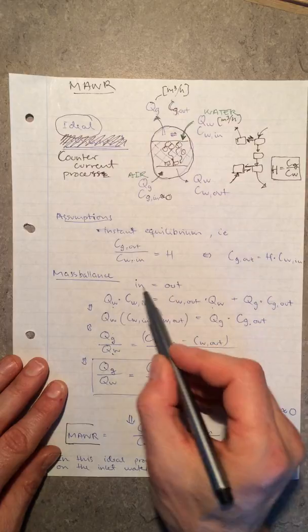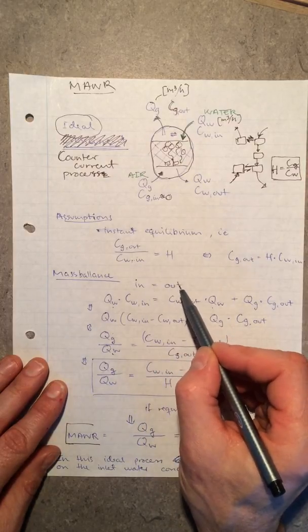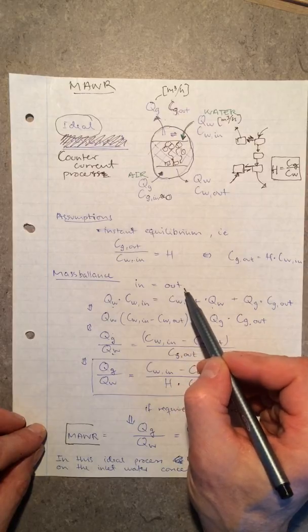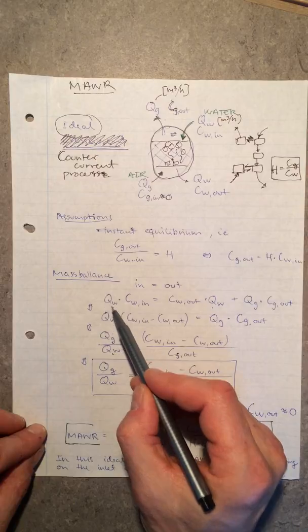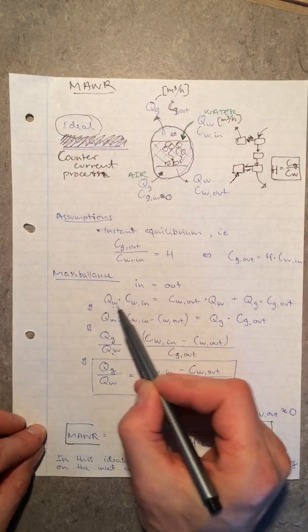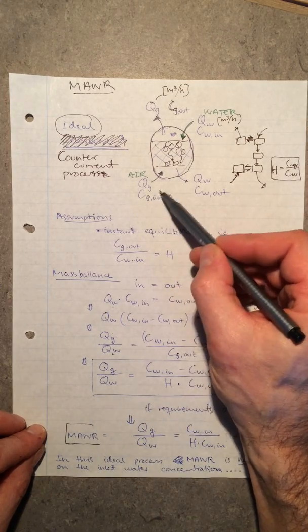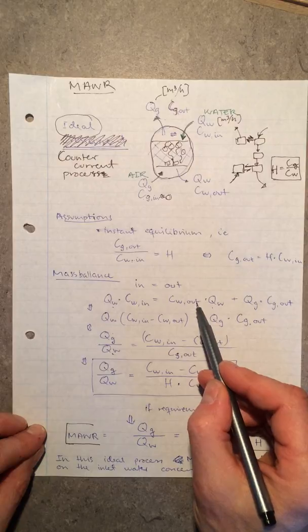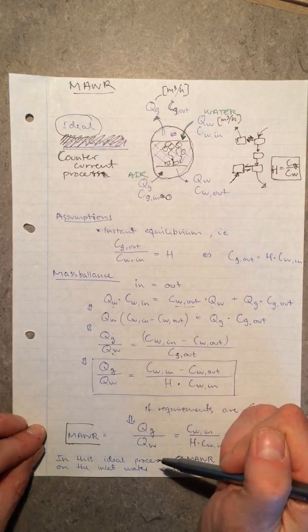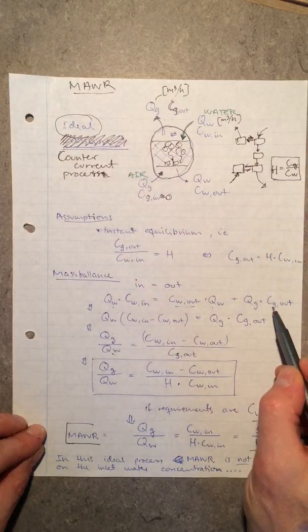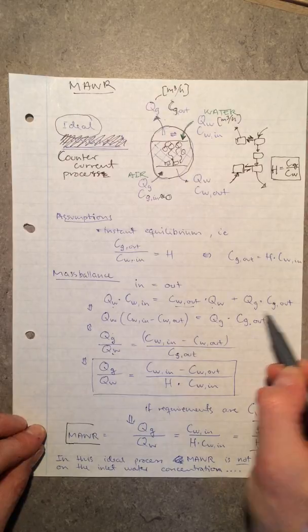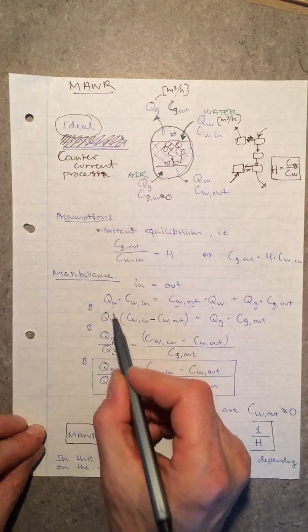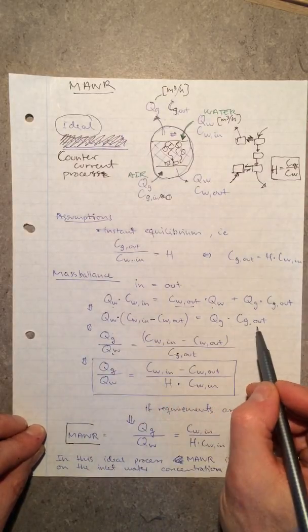If I make a mass balance of substance, I know from this vessel what goes in must come out. For the substance dissolved in air and water, what's going in is going out. Going in is something in the water: I have a concentration in the raw water and a flow of water. The flow of air coming in has no substance, so that term is left out. Going out, I have the flow of water with the remaining concentration, and the flow of gas with its concentration. I can rearrange and put the water flow outside the parenthesis.